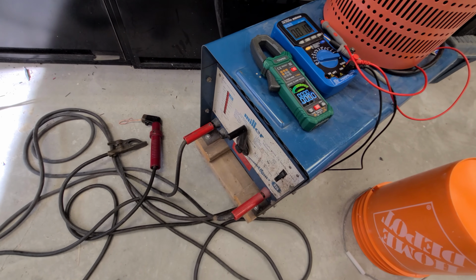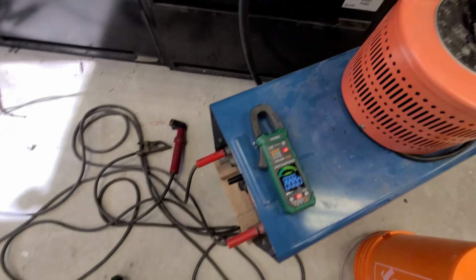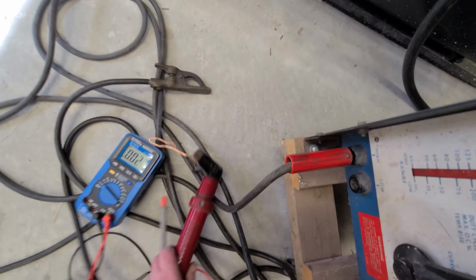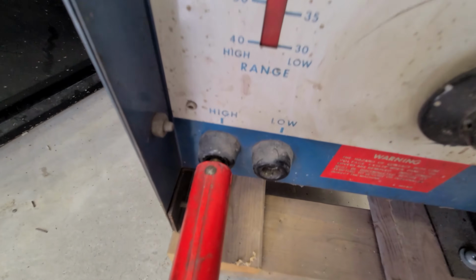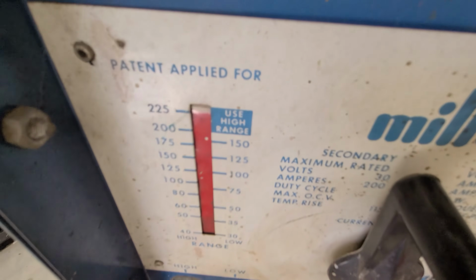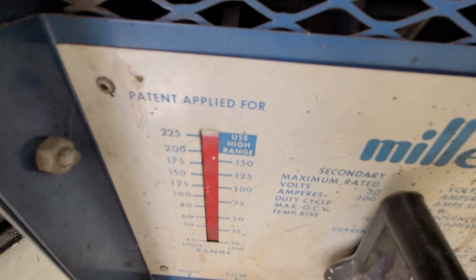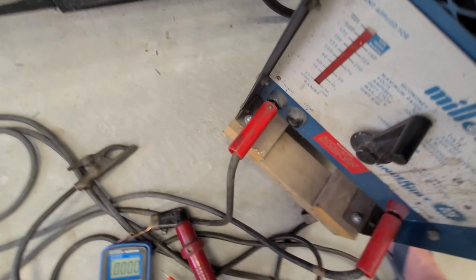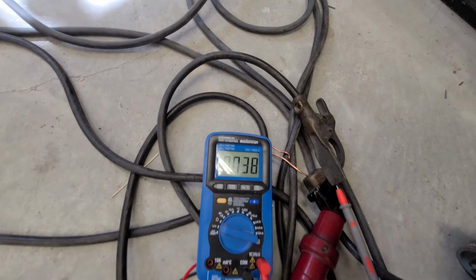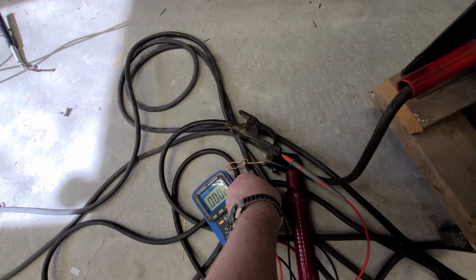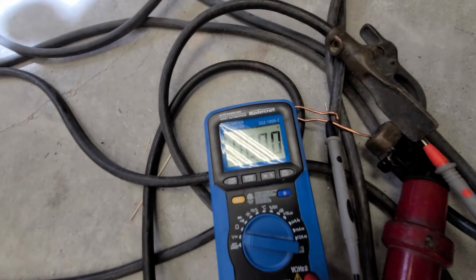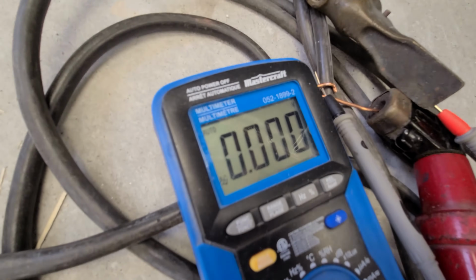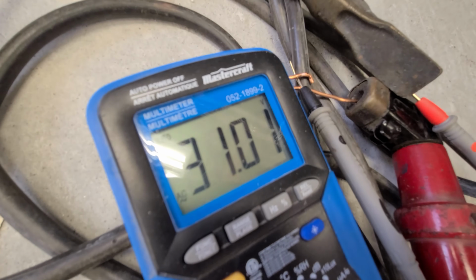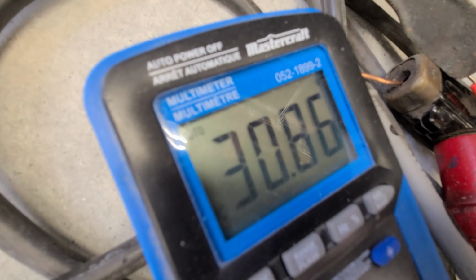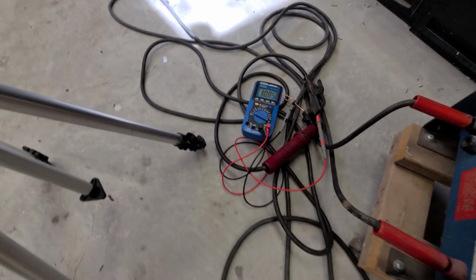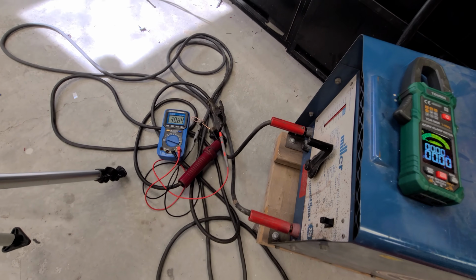So the first thing we're going to do is use a voltmeter to get the open circuit voltage. I have it on the high current setting, at somewhere around 225 amps on the shunt dial. We have the trusty old voltmeter here, and I'm just going to lay this probe there. Hopefully that'll get it good enough. And I'm going to switch it on. What do we get? We get about 31 volts, a relatively low voltage, and that's exactly what we would expect.